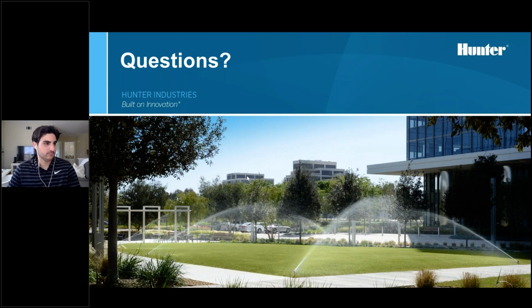Okay, cool. Do you know off the top of your head, I guess not which ones, but can you just allude to EZ1 working with other manufacturers' solenoids? Yeah, absolutely. Like I said, we can run up to 2 Hunter solenoids. So that's ultimately almost half an amp that you can draw from an individual decoder. So we can play friendly with a whole bunch of different solenoid and valve manufacturers out there. It doesn't only play friendly with Hunter valves and Hunter solenoids. Obviously, in a perfect world, we want to have all Hunter product on a project, but if you come across a retrofit site, we can play friendly with a bunch of different manufacturers of solenoids. As long as they're not high inrush current or high holding current solenoids, we typically can operate those no problem.